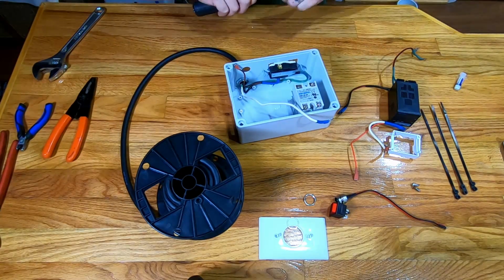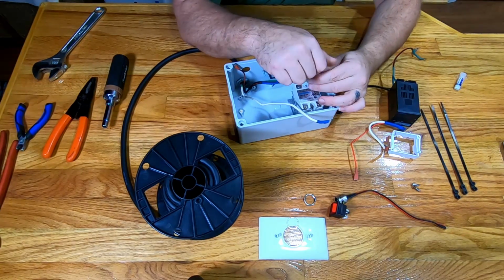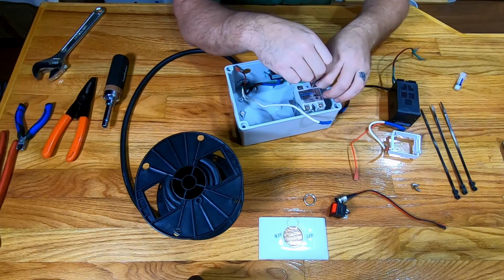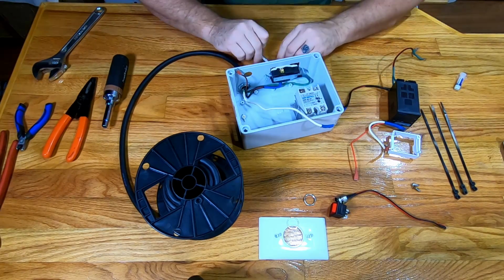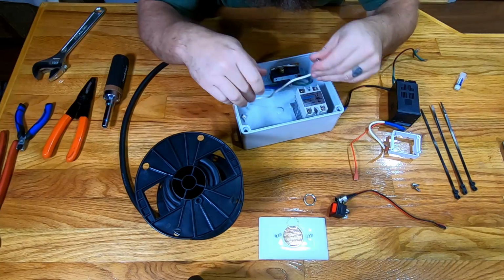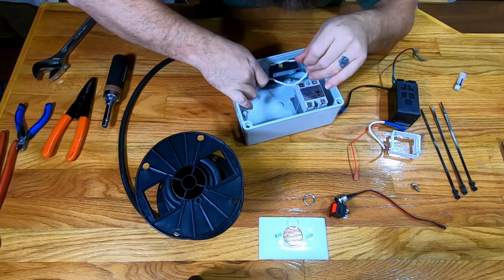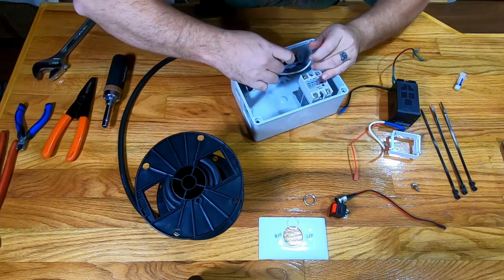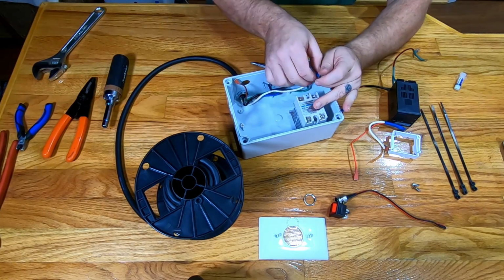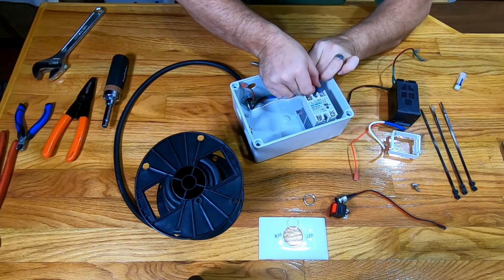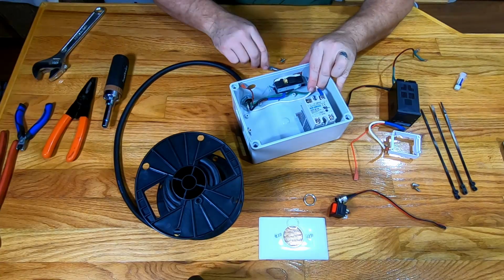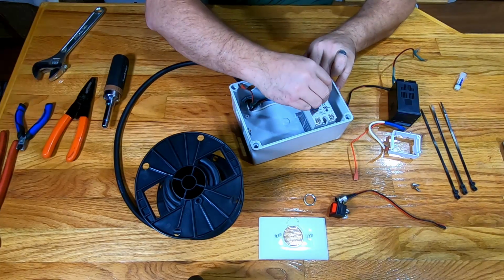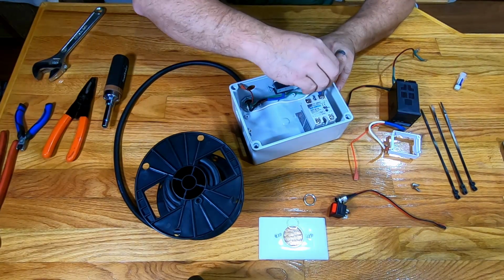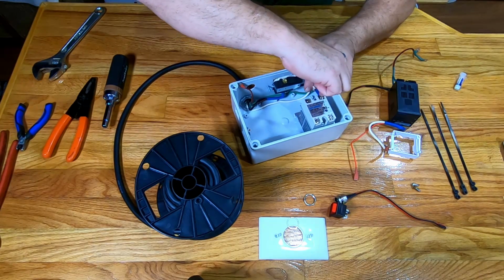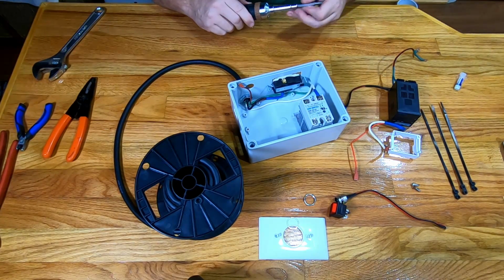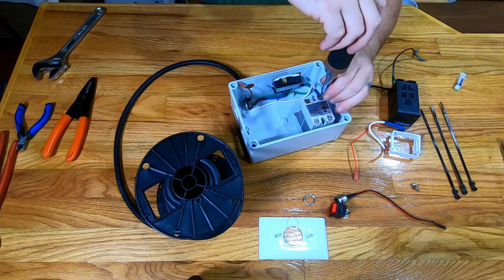Now, the way this system works, and you'll have to look at the wiring diagram once I put it up at the end so you see where all these leads are coming from. But what's going to happen now is this second hot lead - in order for us to have voltage on this receptacle, we've got to have a connection on both sides. So what we're doing now is running the 240 volt input of our relay, which is coming in right here. So that's going to be attached. Now we have power coming into our relay.